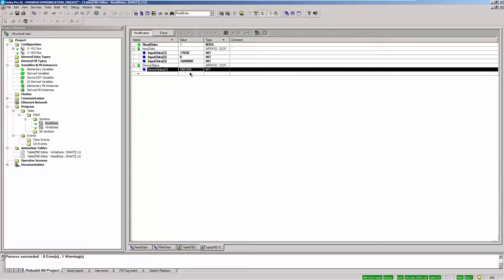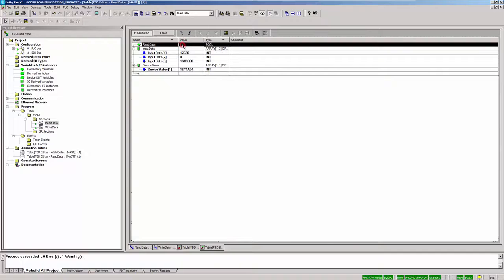The high byte of the status information is the so-called life sign. The value is incremented by 1 with each successful reading of input data from the device. The low byte describes the operating state of the device. The value 4 means that the device is in cyclic data exchange. The high byte of the third register of the input data contains its status. Hex 80 means good. The first two registers of the input data correspond to the value. Repeated reading shows that this data changes.